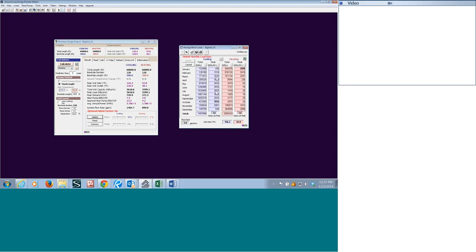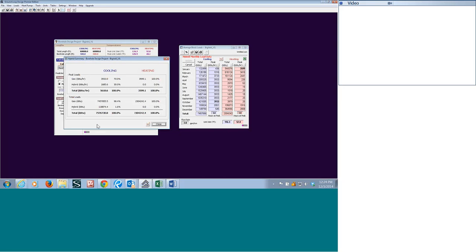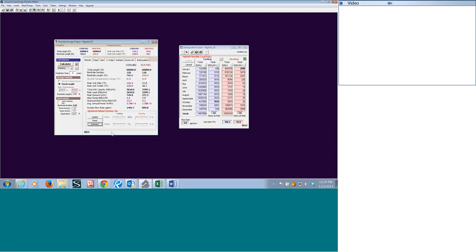We're going to go back to that, and if you'll notice, we have really trimmed these peaks back, and they're all consistent now for the months of April through October. And it's saying for our totals, we've converted about 2% of the total heat rejection to the auxiliary cooling device. So if we looked at a summary of this, our hybrid total BTU capacity that it's going to absorb annually or take off the loop is 118,874.4 kBTU for the total year, and that 2%, that's not very much. So what we're going to do is recalculate this now and see what it does, if it makes a big difference or not.